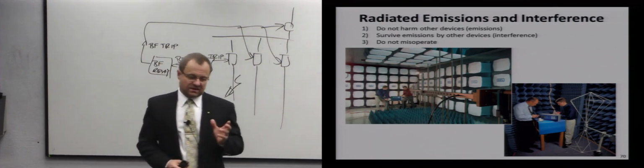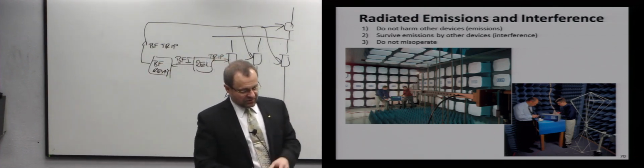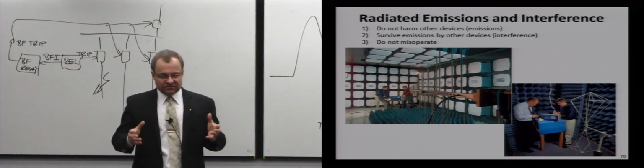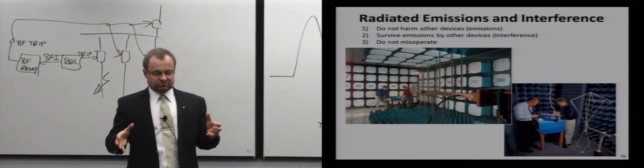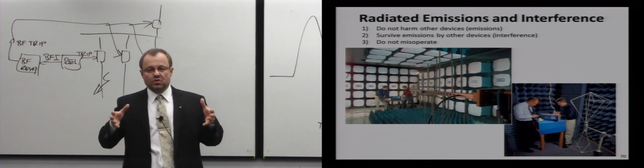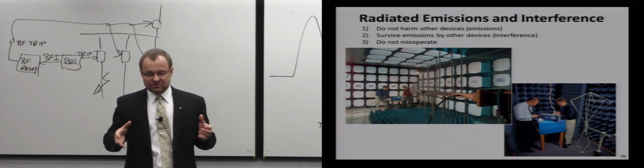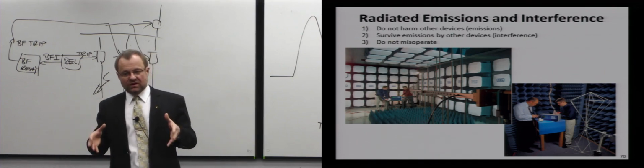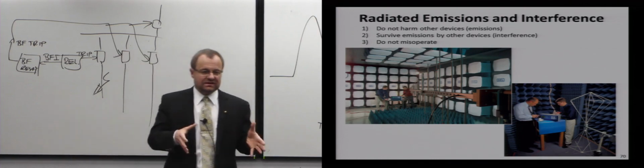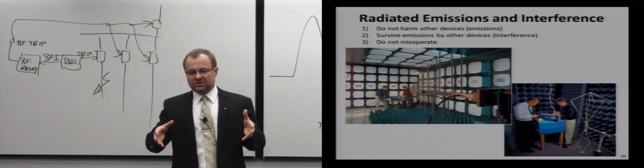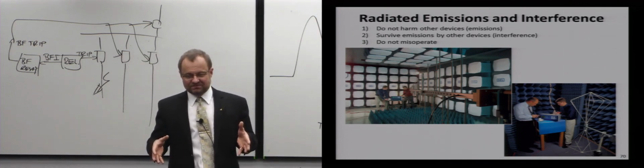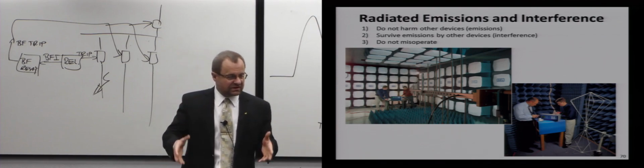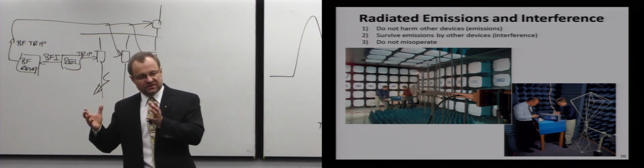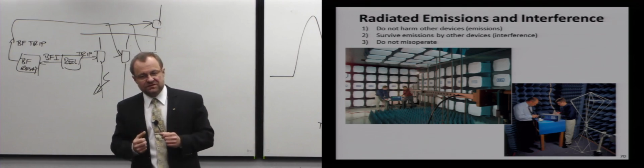I mean, there is an agreement between a couple of parties. So one party is people who build substations. They have to make sure that the environment is quiet enough. So they have to meet certain requirements so that if you put a relay there, those relays are not going to reboot every 2 minutes, right? So it's about proper grounding, proper shielding, proper distance from the primary conductors.